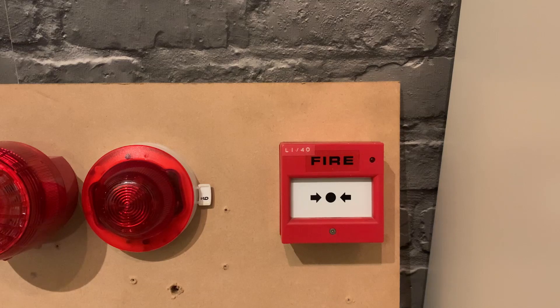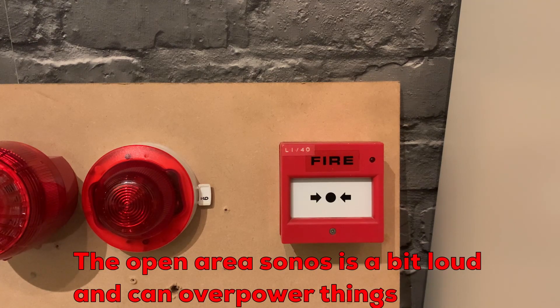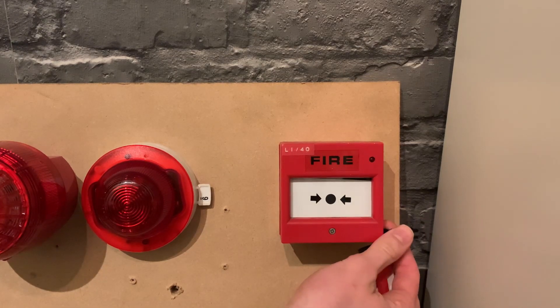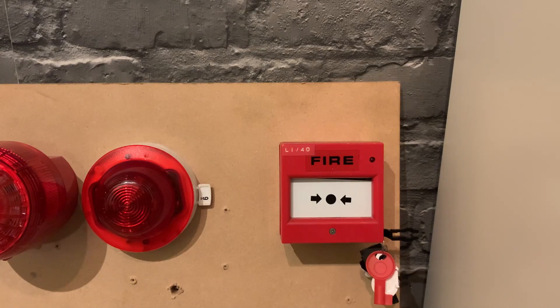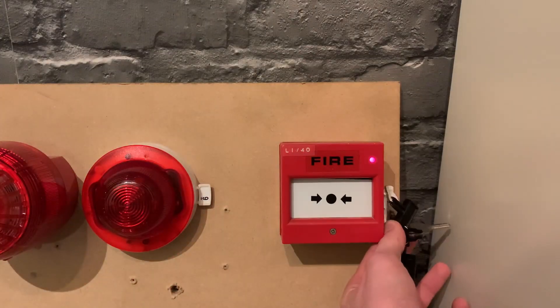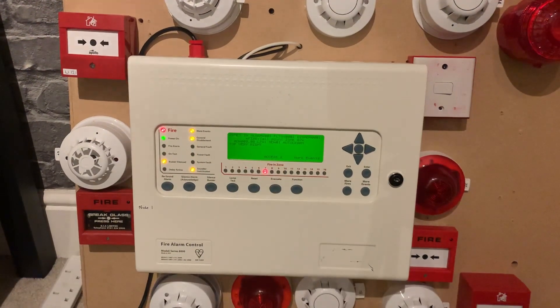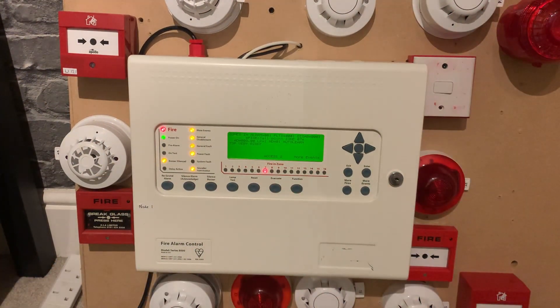We're now going to give the series 90 call point a test. I've reset the system and disabled the open area sounder beacon, so it will just be base sounders for this test. Just going to stick the test key in... and there we have it for that one.